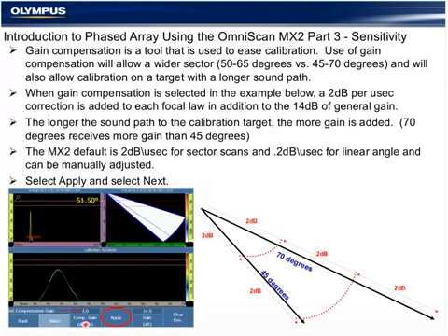So one of the limitations of this display is that no matter what my setup is, my first focal law must be below 100%, and my last focal law must be above approximately 10%. So whether I made the sector scan 45 to 70 or 30 to 80, whatever I'm doing, I've got to maintain that ratio or I'm not able to complete the calibration wizard.